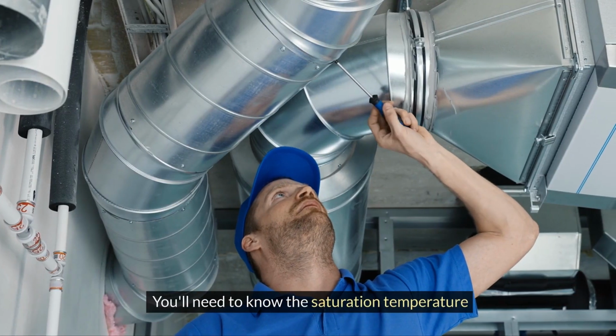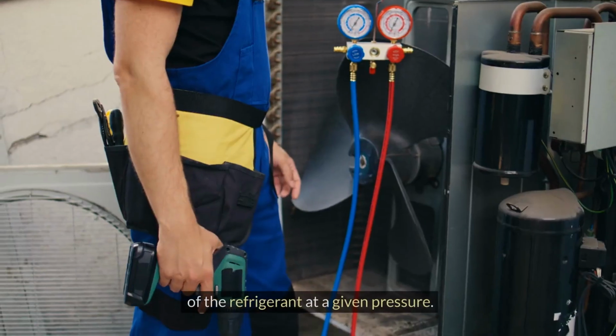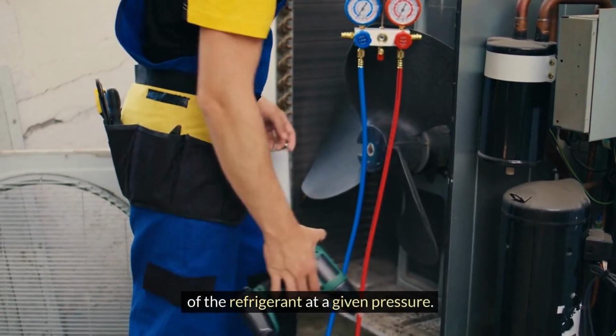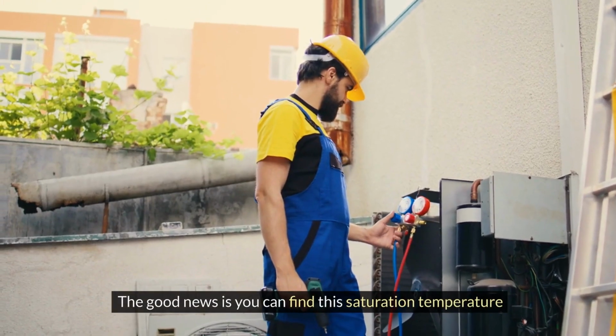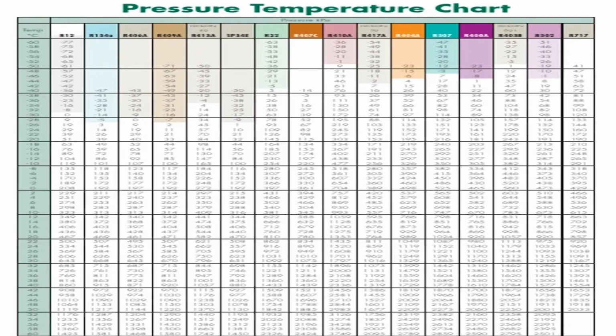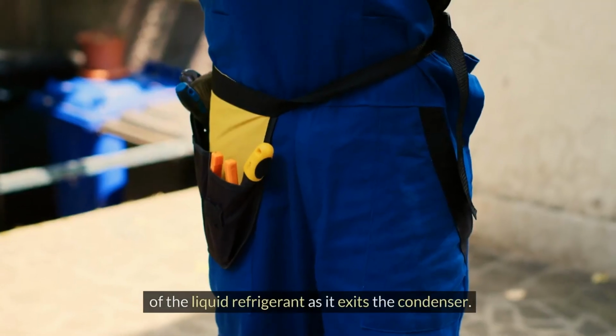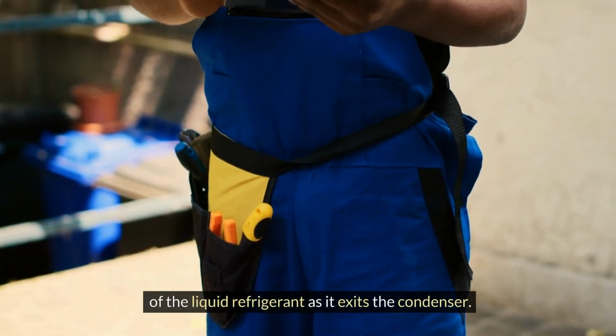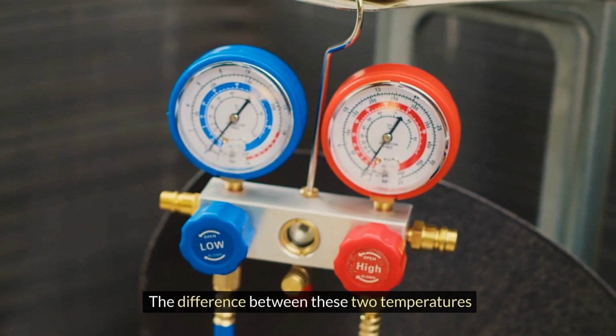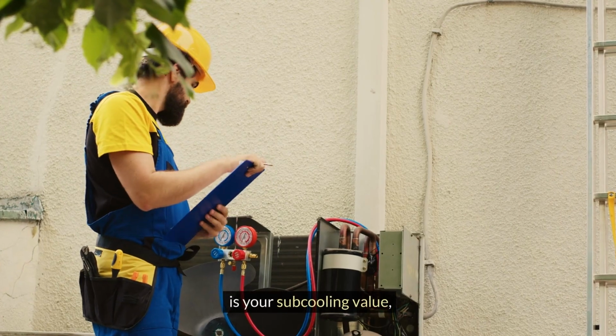You'll need to know the saturation temperature of the refrigerant at a given pressure. The good news is you can find this saturation temperature on a PT or pressure temperature chart. Then measure the actual temperature of the liquid refrigerant as it exits the condenser. The difference between these two temperatures is your subcooling value, typically measured in degrees Fahrenheit or Celsius.